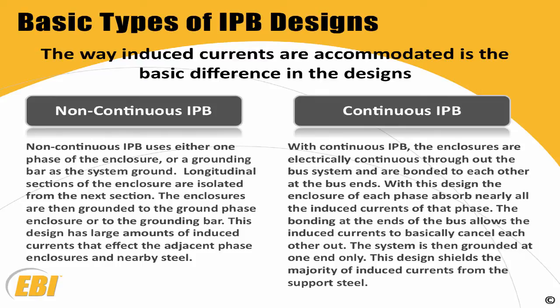The continuous IPB has shorting plates at every end of the bus, at the generator, the GSU, all the auxiliary transformers, the PT cubicle, any tap that comes off of it. It has a shorting plate that bonds the enclosures together. This causes the induced currents to turn around and go back in a different direction. What this does is it basically eliminates 95% of all your induced currents that are in the enclosure at this time.